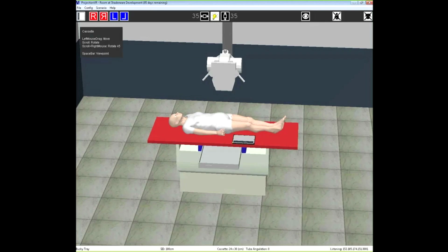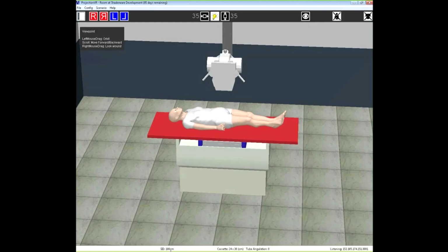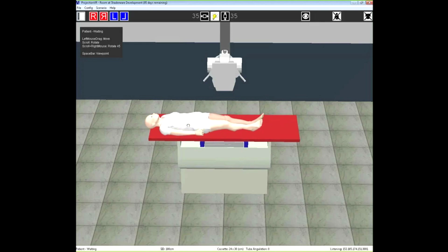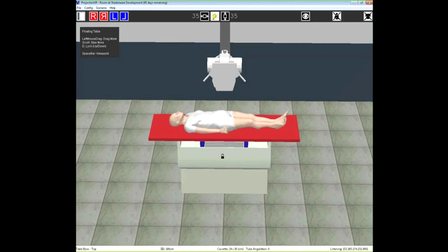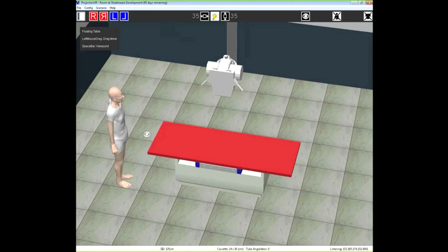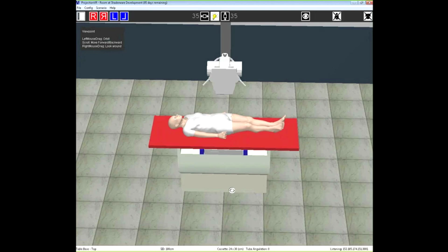If we put the detector in the bucky and then close the bucky, then we're now at 108 centimeters. So if we grab the table base and lower it that 8 centimeters more, then we're at 100 centimeters. So this is much more realistic, and the patient will not leave the table now because they are at a height, and until the table's brought all the way to the bottom, the patient will not leave the table when requested to. So that's much more realistic, we find.